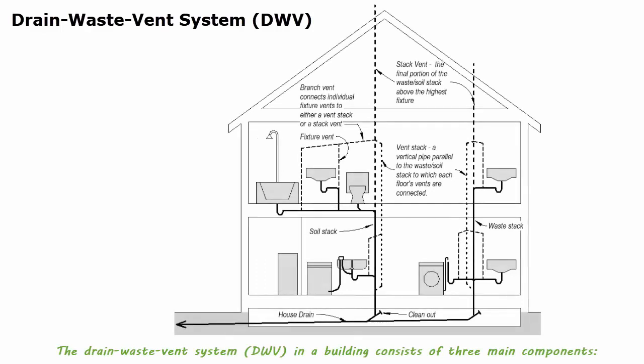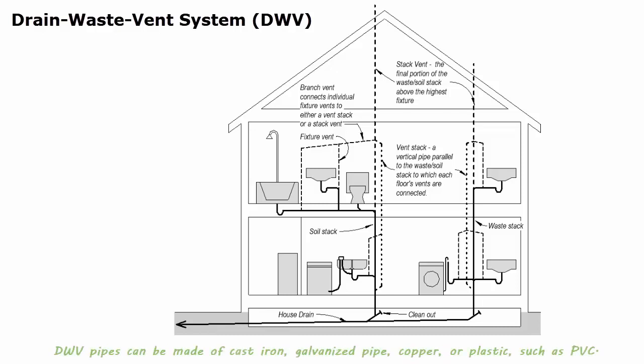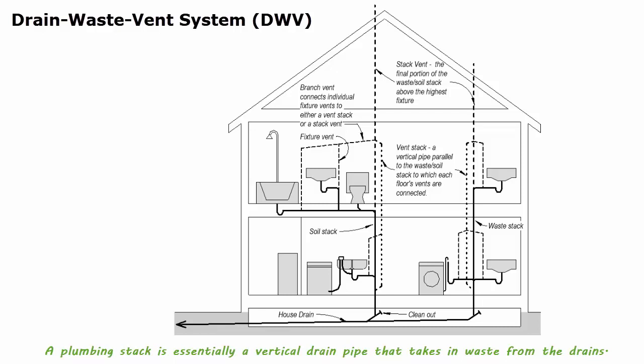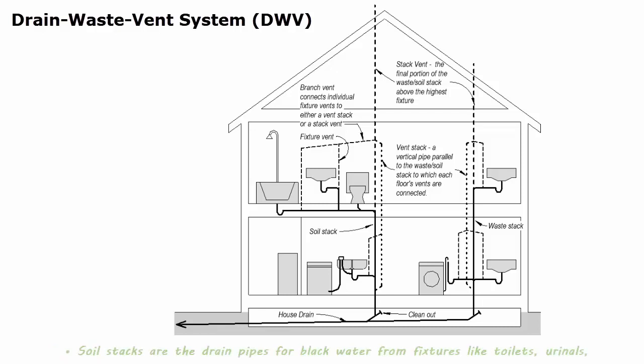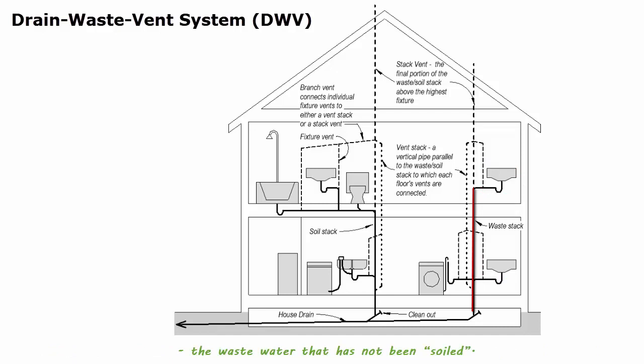The drain waste vent (DWV) system in a building consists of three major components: the drains collect wastewater from plumbing fixtures; the plumbing stacks carry wastewater down to the house drain; and the vent pipes remove sewer gases and allow air to enter the system. DWV pipes can be made of cast iron, galvanized pipe, copper, or plastic such as PVC. A plumbing stack is essentially a vertical drain pipe. Soil stacks are drain pipes for black water from fixtures like toilets, urinals, kitchen sinks, and dishwashers. Waste stacks are pipes that drain gray water from sinks, floor drains, water fountains, and wastewater that has not been soiled.